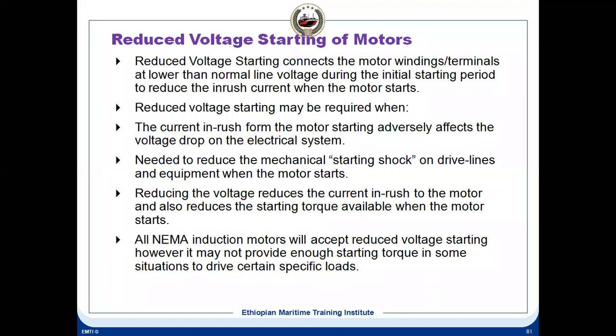In star delta, we are applying a reduced voltage, because in star the phase voltage becomes 1/√3 of the line voltage. So it runs at low voltage first, and once it picks up speed, it changes over into delta. That changeover can be a jerk. These things will not take place in the case of a soft starter. It's a smooth starting. So that is why we are using a soft starter. A soft starter is used only for starting. A VFD can also be used for starting, but a VFD can be used for starting as well as speed control. Star delta starters, auto transformer starters, and soft starters are used only for soft starting purposes.